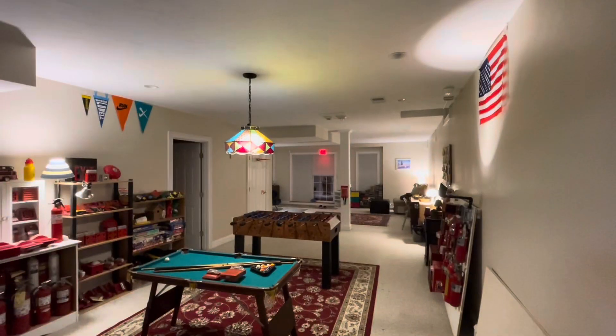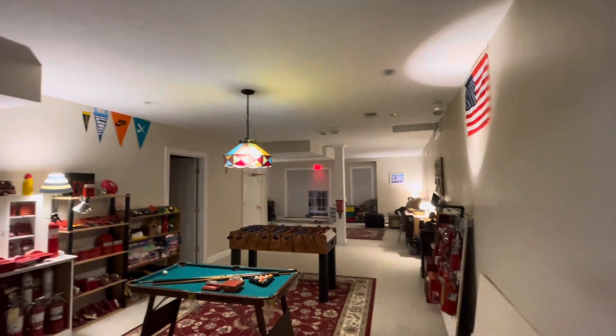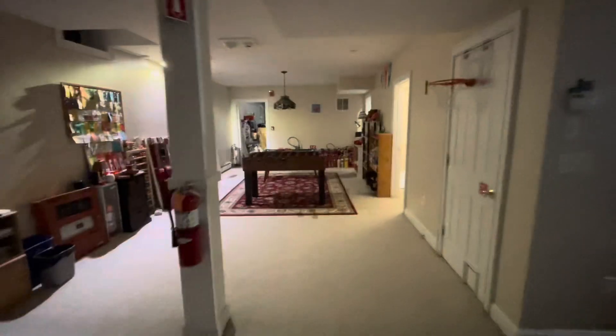Let's go ahead and turn the power off for real. With Dual-Lite products, when you turn off the power all the lights go off for about two seconds and then the emergency lights turn on — it's actually a cool effect. Three, two, one — all lights are out. Check that out — this thing lights all the way back there, the beam goes all the way over here. It's quite bright; for such a small unit, this space is quite well lit.